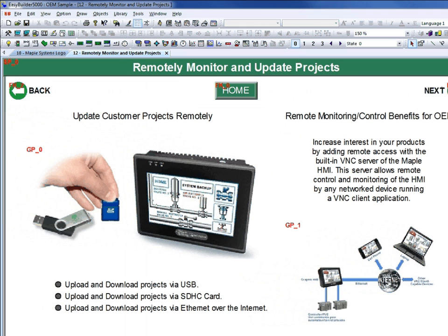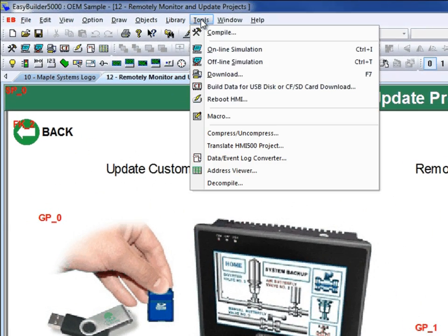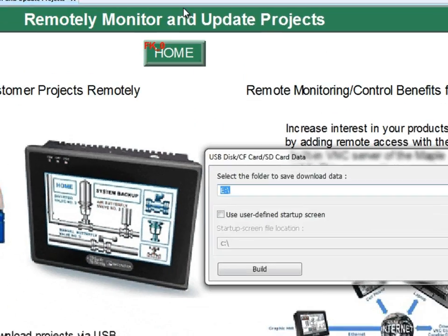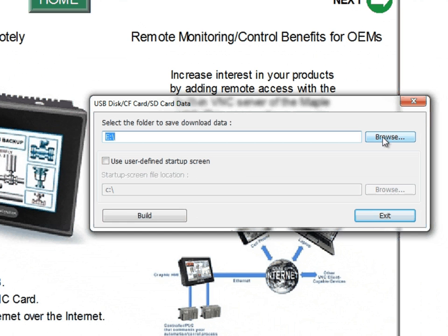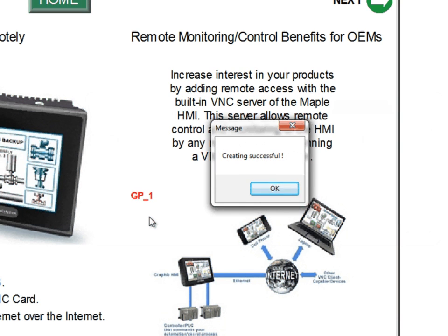One of the best features of the Maple Systems HMI is being able to update a project without having to go to the field. To do this, first you have to build data for a USB disk or SD card. Go to the Tools menu and select 'Build data for USB disk or CF SD card download.' Select the directory you want to save the data to and click the build button. This will build data that can be automatically downloaded to your HMI via USB or SD card.